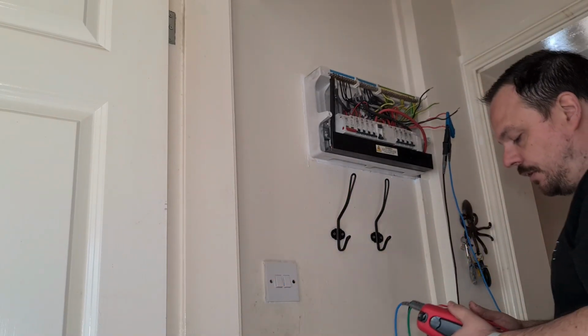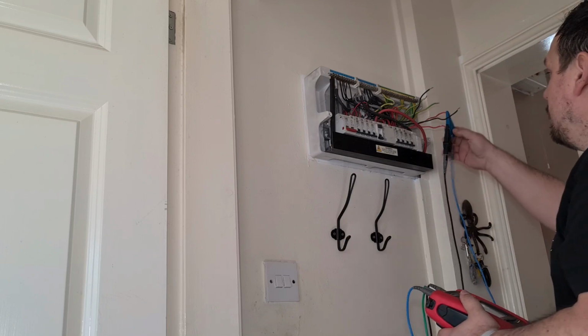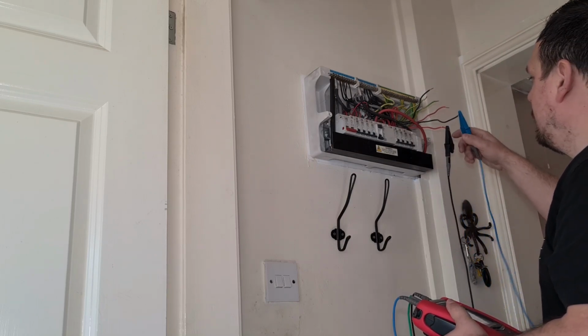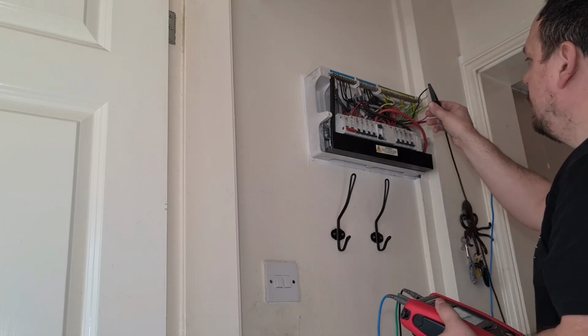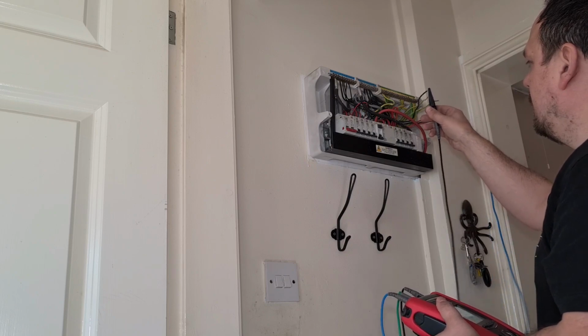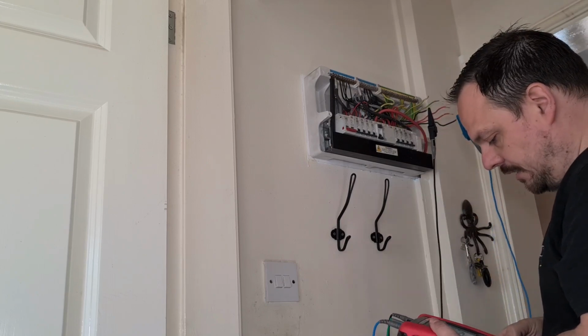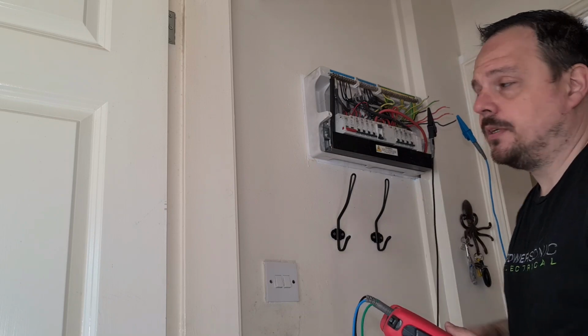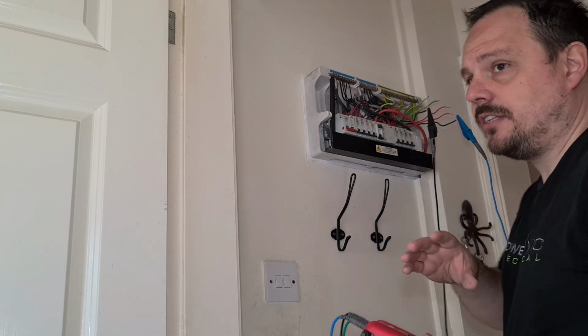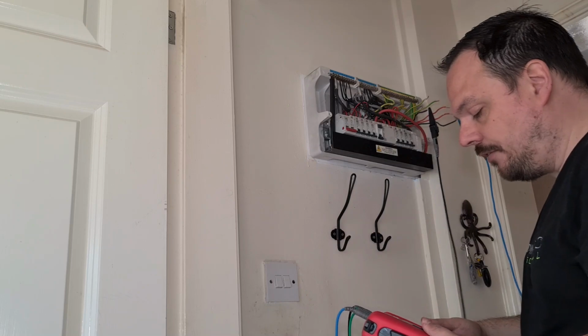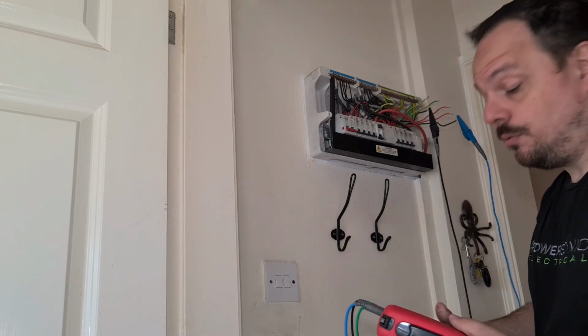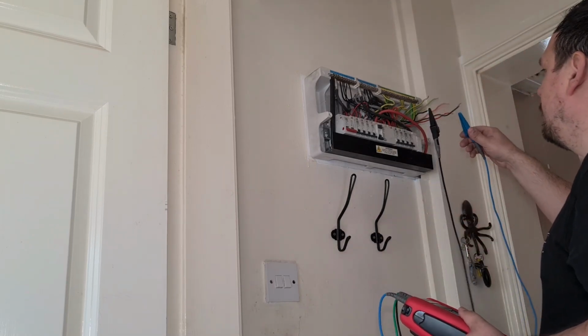We've got 0.21 ohms, so we should find on the neutral, your little rn, roughly the same. Obviously there'll be slight variation because of the way the cables are dressed at some of the accessories - they could be longer or shorter - but there or thereabouts, it's 0.23 ohms. So we're happy with that one.